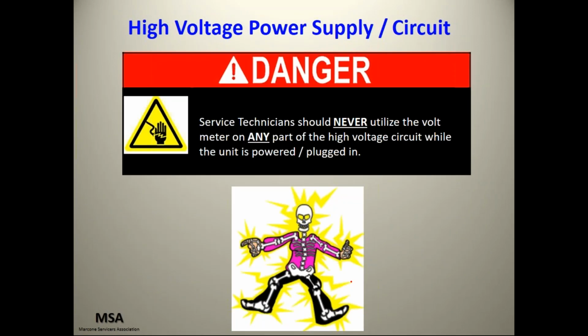Okay, into the microwave itself, the high voltage power supply circuit. I like to have fun when I'm doing training. This is definitely not a fun thing. The high voltage in here can put you out of commission, especially if you have heart issues or if you have a pacemaker or something of that nature. You're looking at 4,000 volts in here with a fairly good amount of current. Service technicians should never utilize the voltmeter on any part of the high voltage circuit while the unit is powered or plugged in. Be very, very careful.